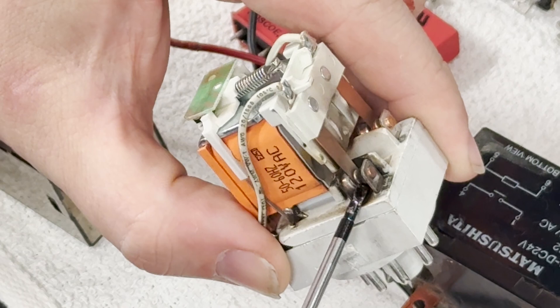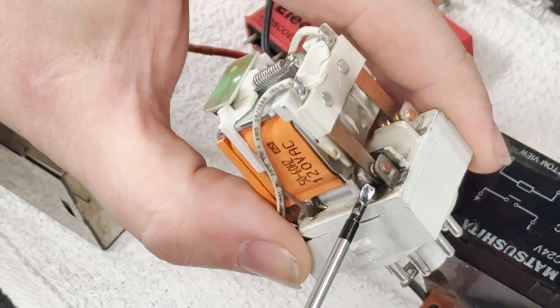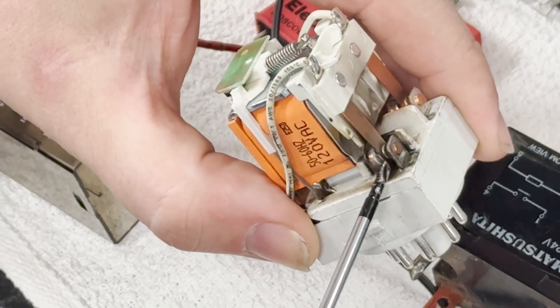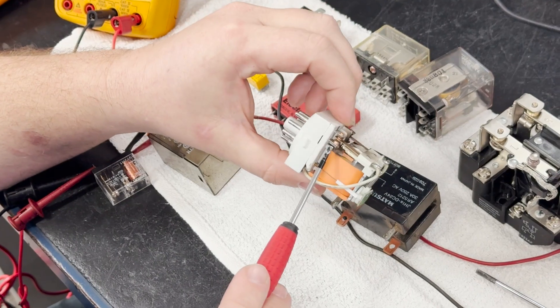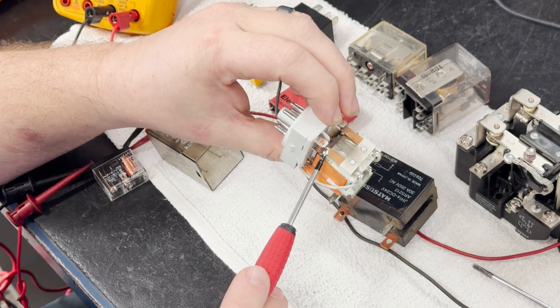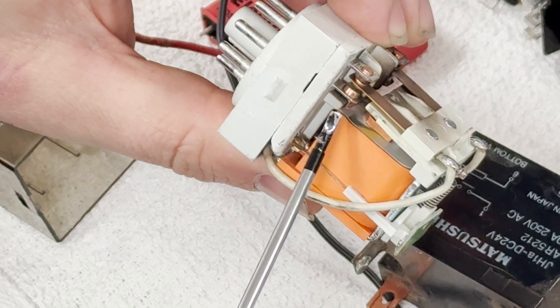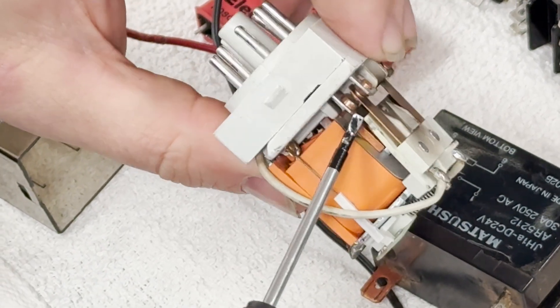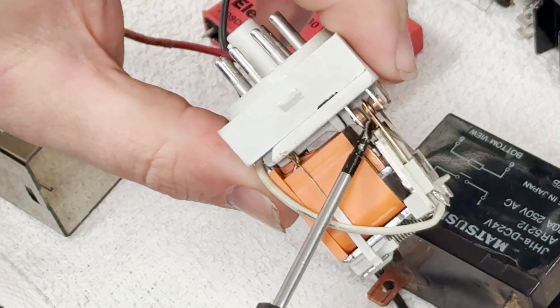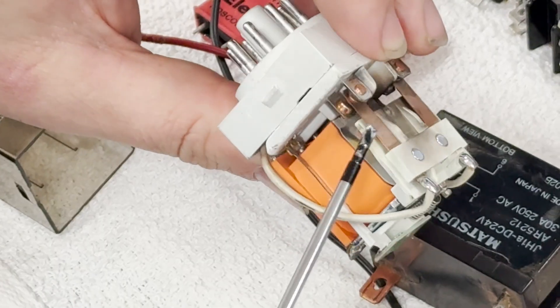This carbon buildup happens from many, many activations of this relay over time and absolutely builds up until it eventually fails. Here on the other side, you can see that this side of the relay is used less frequently, or maybe not at all depending on the customer's application. You can see this set of contacts are relatively clean without any carbon or corrosion on them.